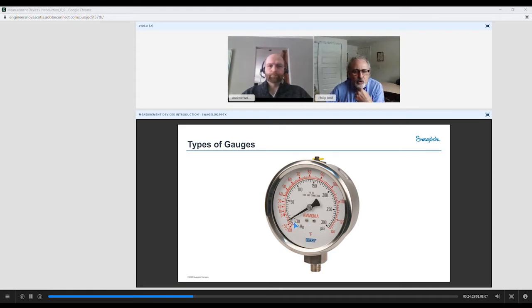And ammonia has the same. So as you pressurize ammonia in large refrigerant systems, it correlates to a specific temperature. And you can see here we have it marked in Fahrenheit and PSI here, and inches of mercury in a negative pressure situation.